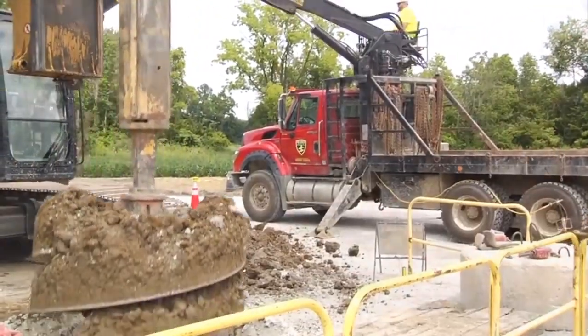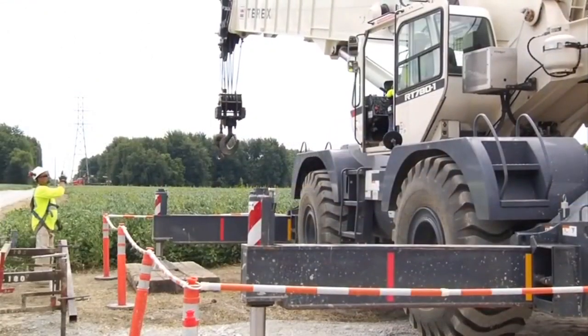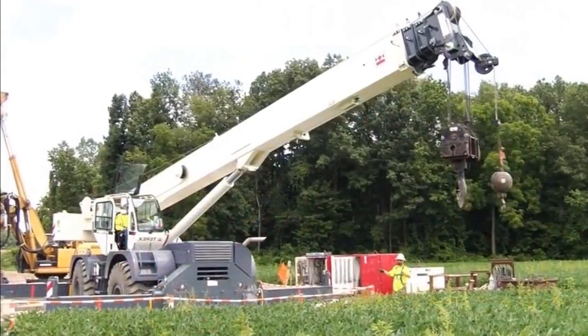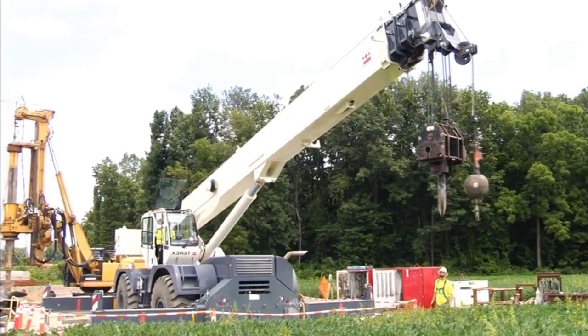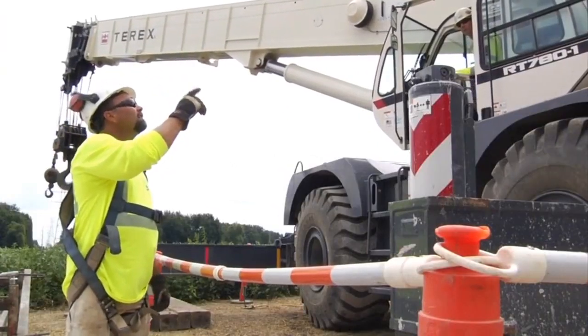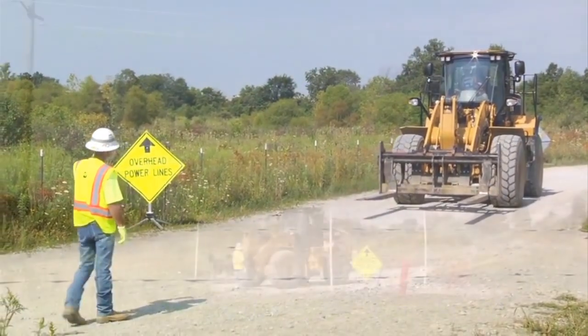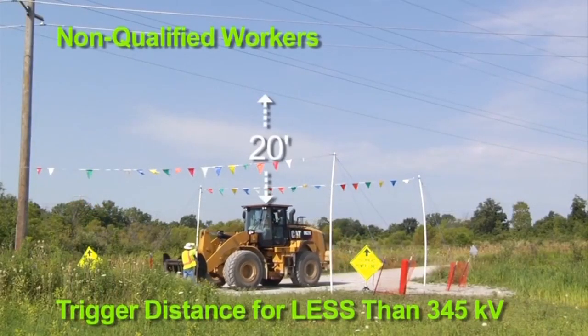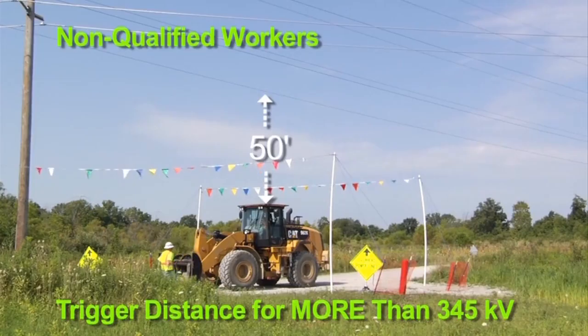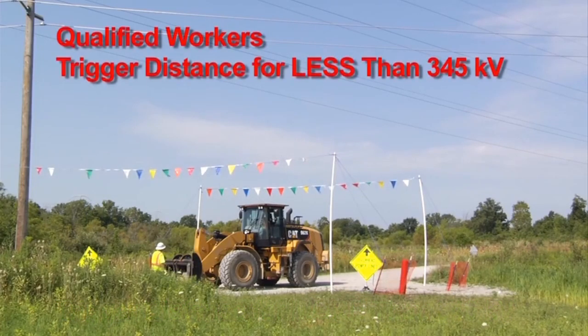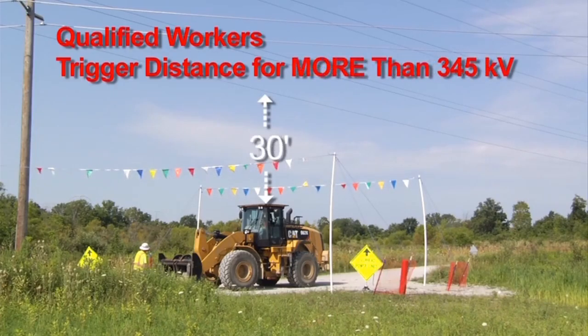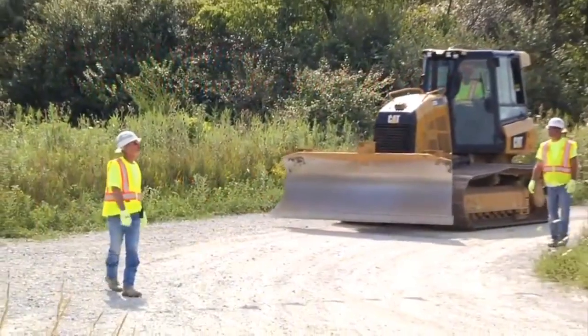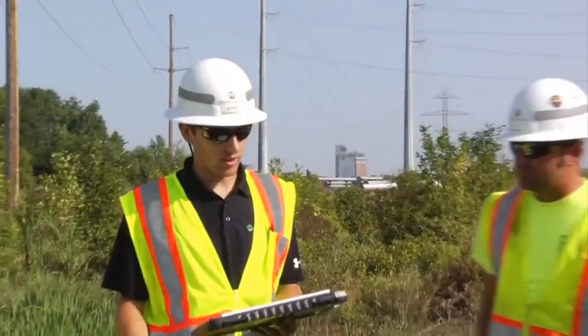Mobile equipment such as trucks, excavators, bulldozers, and cranes may be at your worksite. Before beginning equipment operations, the contractor shall identify the work zone to determine if any equipment or any part of the equipment's maximum working radius, including the load, load line, boom, and lifting accessories, could encroach the trigger distance to energized lines or equipment. The trigger distance for non-qualified electrical workers is defined as 20 feet for less than 345 kilovolts and 50 feet for 345 kilovolts or greater. For qualified electrical workers, these distances are defined as 15 feet for less than 345 kilovolts and 30 feet for 345 kilovolts or greater.